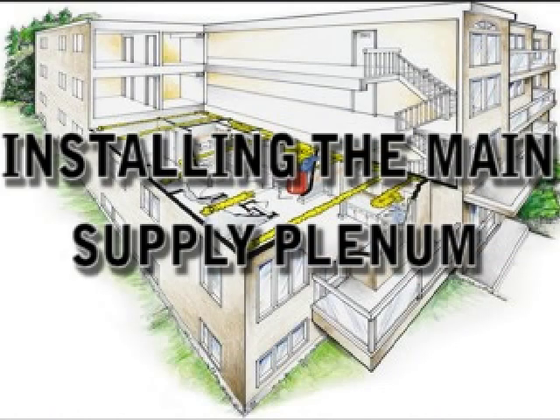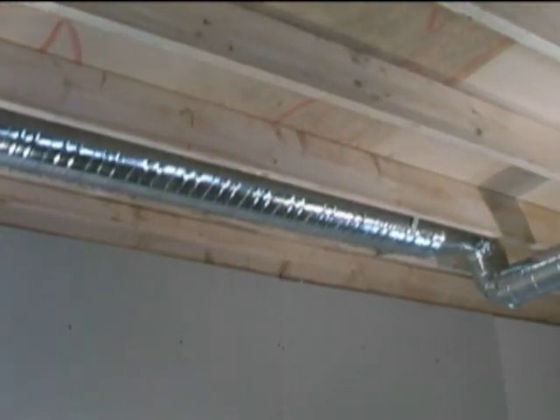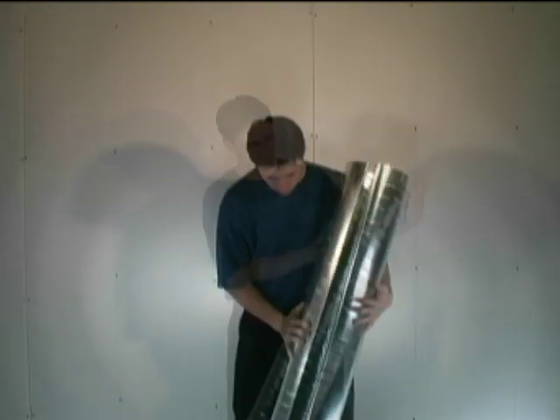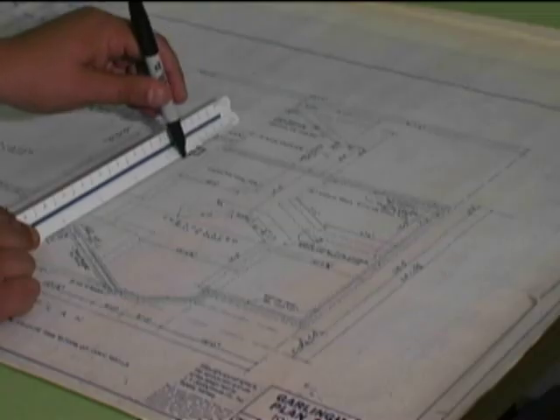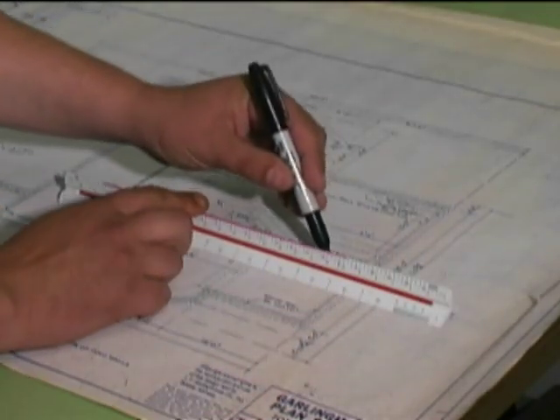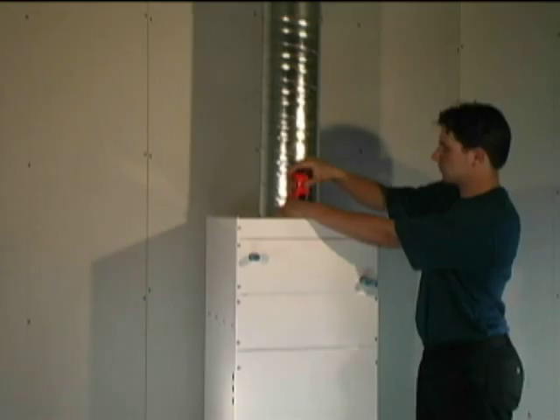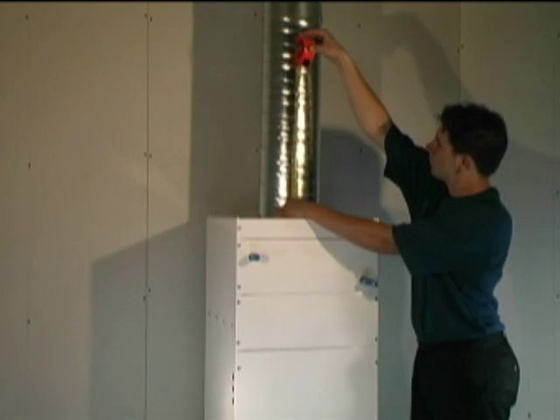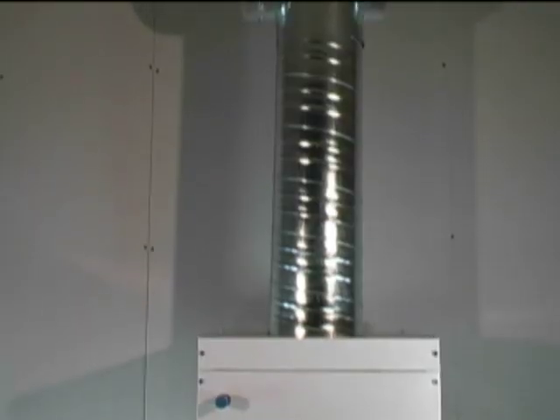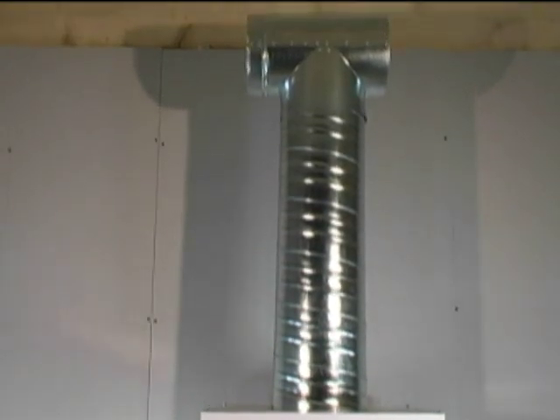Installing the main supply plenum. Two types of duct are recommended for use with the High Velocity System: spiral duct or snap lock duct. The main plenum should be located according to the design layout. Before beginning work, inspect the location of the duct to ensure there are no obstacles. It is essential that the main supply plenum extend a minimum of 18 inches from the fan coil before any elbows or T's are installed.